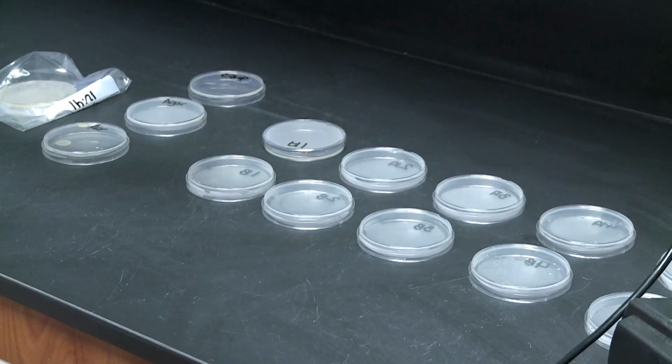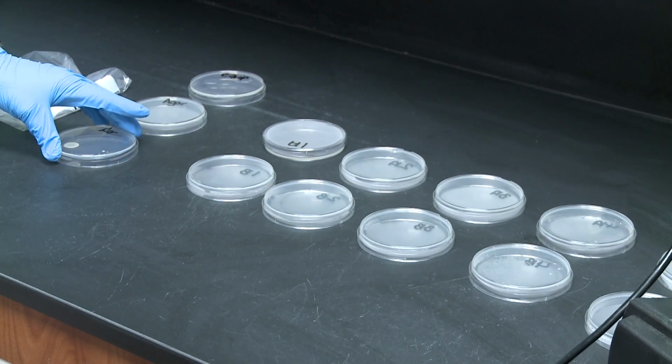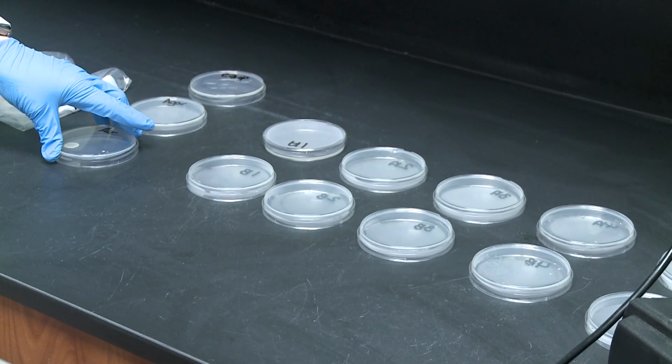A boil water advisory is going to last usually from 24 to 48 hours. The duration is going to depend on how long the crews can get out there and isolate the issue. They're going to need to either make the repair under pressure, and if that can't be done, then they'll lose pressure. Then we're going to have to maintain that pressure back up at 20 psi. We'll need to make sure our chlorine residuals are up to a minimum of 0.2 milligrams per liter for adequate disinfection. And then we're going to need to get out there and do some monitoring, and the monitoring itself actually takes 24 hours to incubate the sample and get results back.